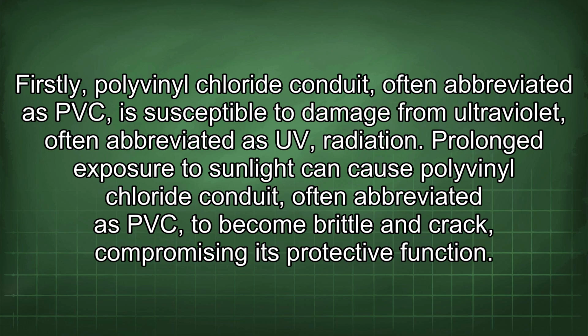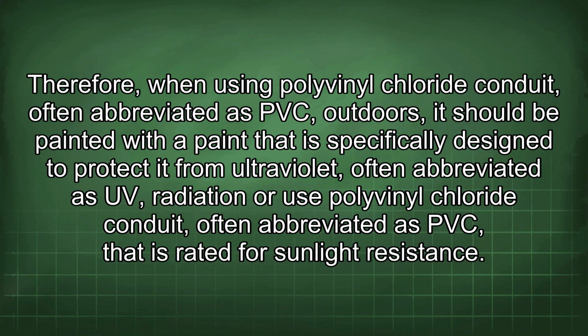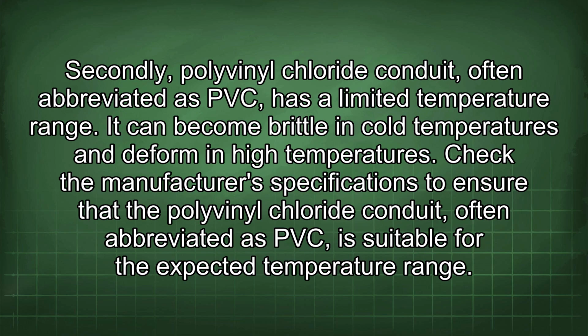Prolonged exposure to sunlight can cause PVC to become brittle and crack, compromising its protective function. Therefore, when using PVC outdoors, it should be painted with a paint that is specifically designed to protect it from UV radiation, or use PVC that is rated for sunlight resistance. Secondly, PVC has a limited temperature range. It can become brittle in cold temperatures and deform in high temperatures. Check the manufacturer's specifications to ensure that the PVC is suitable for the expected temperature range.